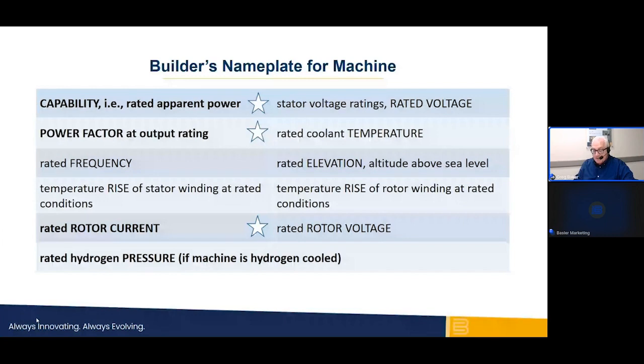In our work to size a new excitation system for a client's existing machine, we make use of the nameplate, or at least a transcription of the values memorialized in the nameplate. Our concern with establishing excitation limiters draws our attention to the machine's capability, its rated power factor, and its rated rotor current. See my stars on the slide that highlight those three things.